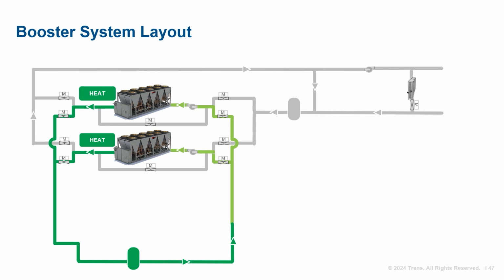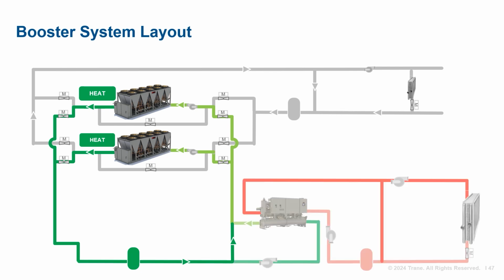Instead of sending the warm supply to the building, a booster heat pump can be added between the air-to-water heat pump and the building hot water distribution to achieve much higher hot water supply temperatures. Since the air-to-water heat pump is controlled to a lower hot water supply temperature, 75 degrees Fahrenheit for instance, the air-to-water heat pump capacity and efficiency is improved. To keep the control simple, and since the flow rates are often selected near the unit minimum, both the evaporator and condenser side of the booster are piped in primary-secondary arrangement.